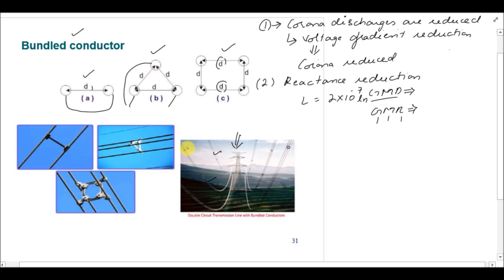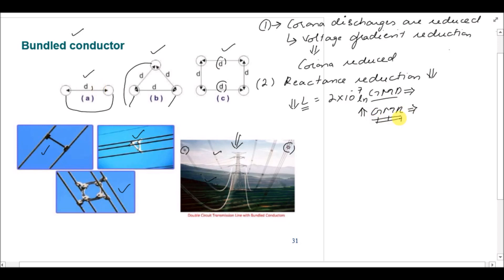This is a double circuit line, which we will discuss later in remaining lectures. This is the actual figure of bundled conductors — with two conductors bundled, three conductors bundled, or four conductors bundled. To reduce the reactance, we have to reduce the inductance. To reduce the inductance, the GMR has to be increased, and for the bundle conductor the GMR is automatically increased.